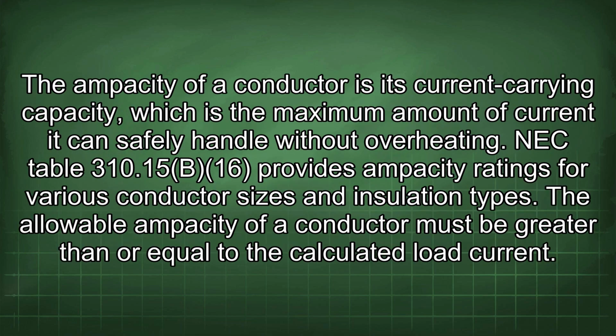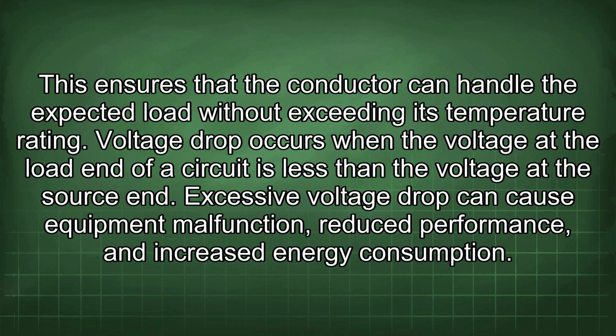The ampacity of a conductor is its current carrying capacity, which is the maximum amount of current it can safely handle without overheating. NEC Table 310.15(B)(16) provides ampacity ratings for various conductor sizes and insulation types. The allowable ampacity of a conductor must be greater than or equal to the calculated load current. This ensures that the conductor can handle the expected load without exceeding its temperature rating.